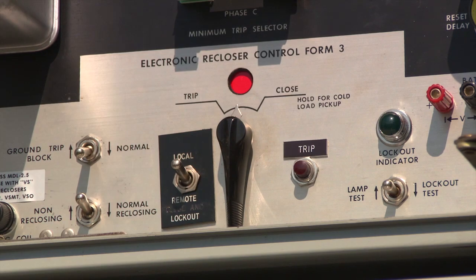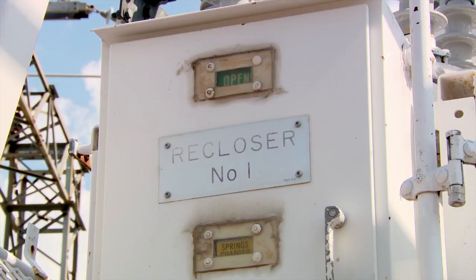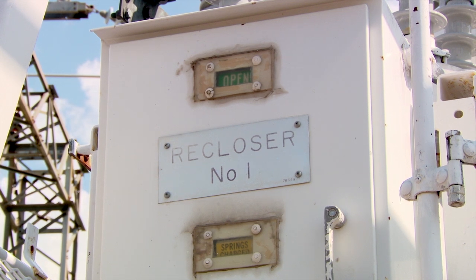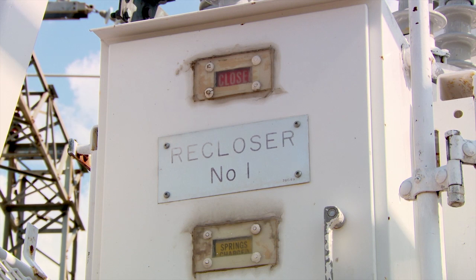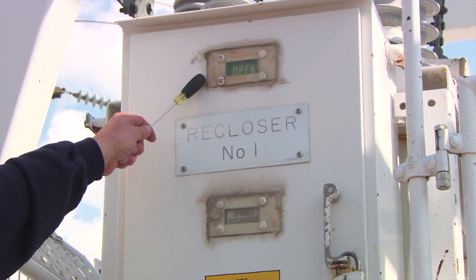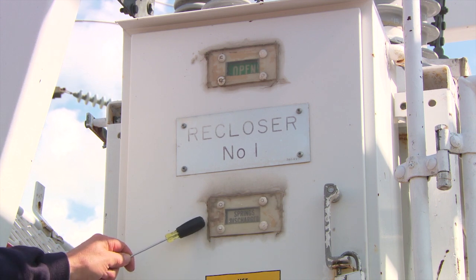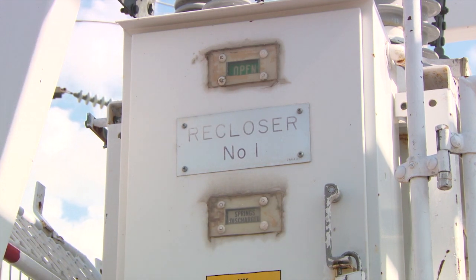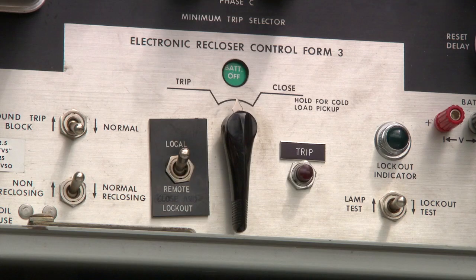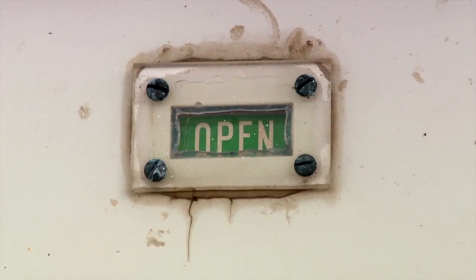The contact position indication is linked to the main operating shaft and is visible through the window on the cabinet. The closing spring charge state indicator indicates whether the springs are charged or discharged. This is also visible through the window on the cabinet door. Closing springs are charged by a motor drive that provides energy to close the main contacts and simultaneously charge the opening springs. The opening springs are located in the recloser spring mechanism.